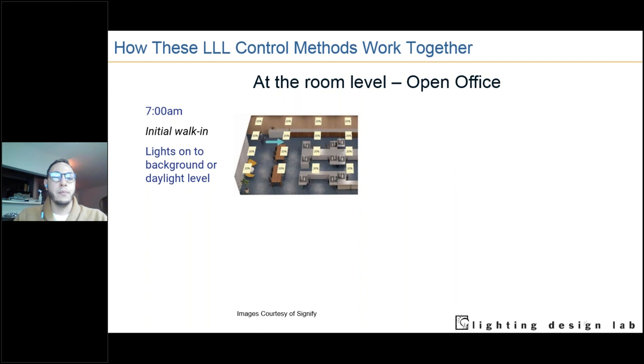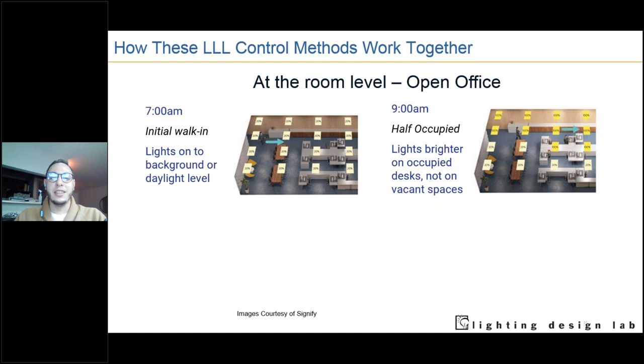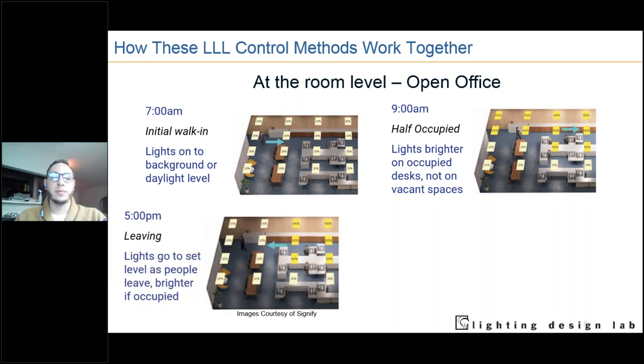Consider when the office opens at 7 a.m.: people are initially going to be walking in, and not to have the lights turned off, but through a schedule, you can have these lights turn on to what they call a background level. Have these lights turn on to 20% just to allow for safety and ensure that people walking in are comfortable. They don't walk into a very bright space that glares at them and blinds them. But as people keep coming into the space and sitting at their desks, the lights are going to be a lot brighter to show that everyone has visibility to their task. But other spaces where people have not come in yet will still be at that background level, again just keeping the comfort for the occupants already in their space.